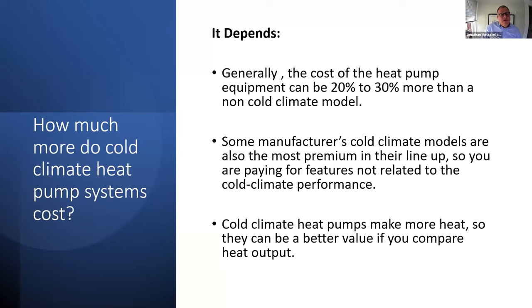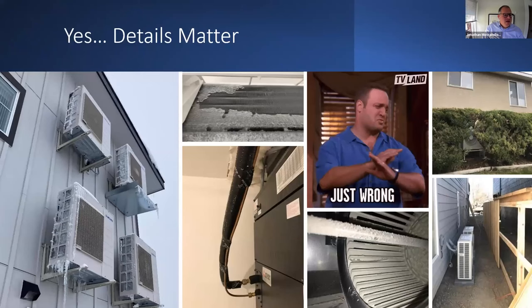But I'd like to point out that when you buy a heating appliance and heating and cooling appliance, you're paying for the ability of that machine to make BTUs. And in my experience, looking at lots of performance tables of these units over the years, I found that the amount of heat produced by a cold climate model is much more. And so dollars spent per BTU created, I think that the cold climate heat pumps ultimately become a better value. I'm speaking in generalities here. Every model is a little bit different. But in my experience with the brands that come out of Japan that I've been most familiar with over the years, I can say that this can be the case for cold climate models.